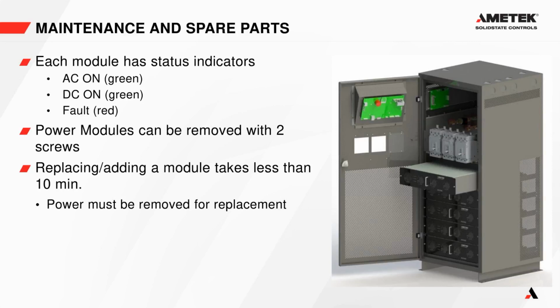The power modules can be removed with 2 screws, and there's a handle to pull them out. They slide out on rails fairly easily. Replacing a module takes less than 10 minutes, but we do not support hot swapping of modules. The power must be turned off to the system before a module can be removed and a new one inserted. And we have some YouTube videos available on our website or on our YouTube channel that demonstrate the module replacement process.